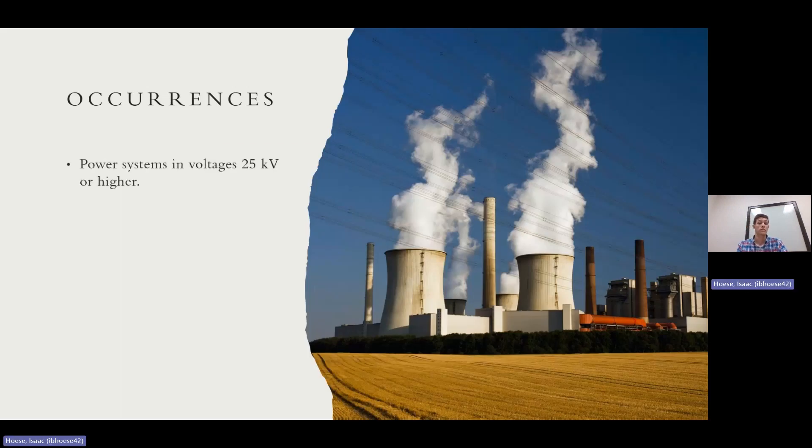Occurrences. So where does ferroresonance occur? Obviously, we said power systems. Most of the time it's 25 kV or higher. It has been known to happen in 12 kV systems as low as that, but the scenario has to be just right for that to happen.